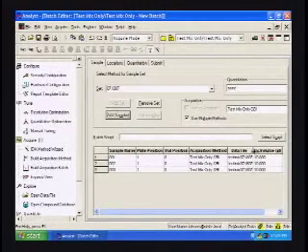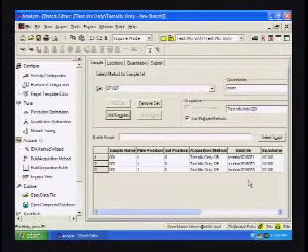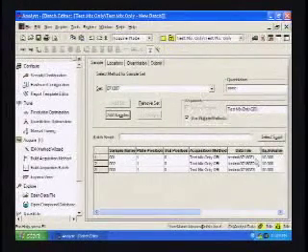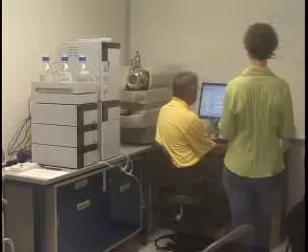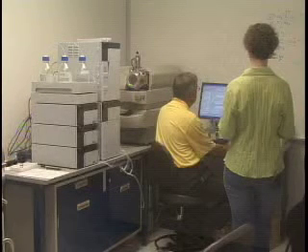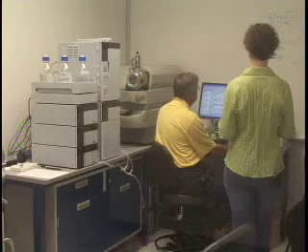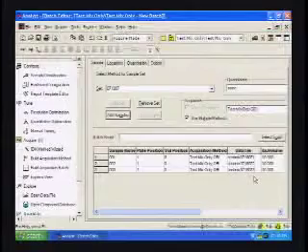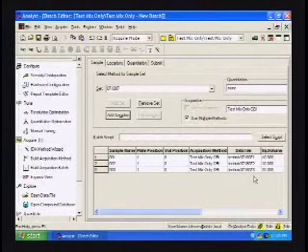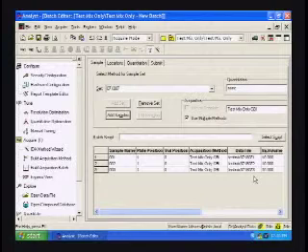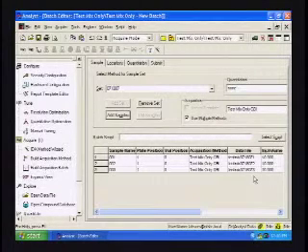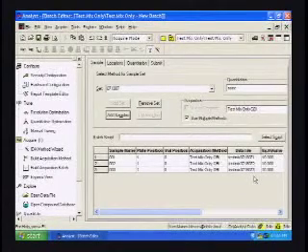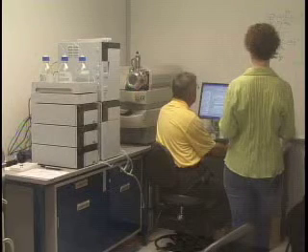At this point, if we wanted to, we could change the file name. Here you can see these are the individual file names. Ends in 0, ends in 1, 2, and 3. Now what it has done for those data files is it went ahead and automatically auto incremented the data files. So what you'll have is you'll have three individual file folders with one injection's worth of data. If you want one file folder with three injections worth of data, you don't want to auto increment. And my recommendation is in most cases you do not want to auto increment. It makes it easier to flip between pieces of data if you don't auto increment.